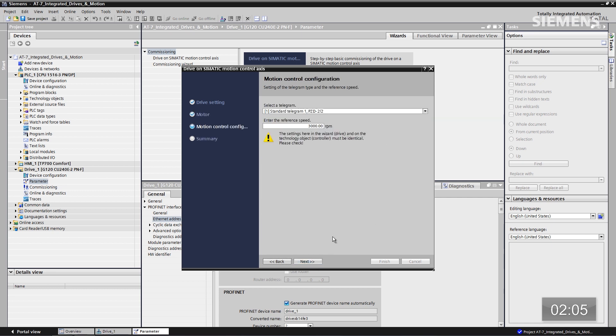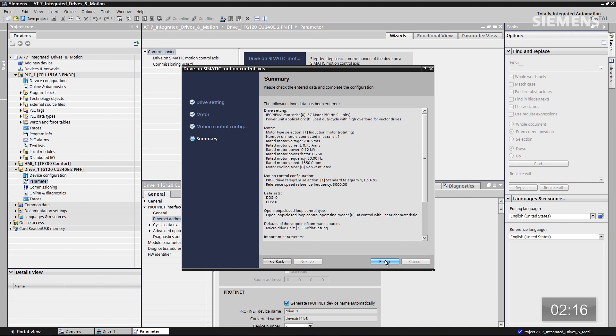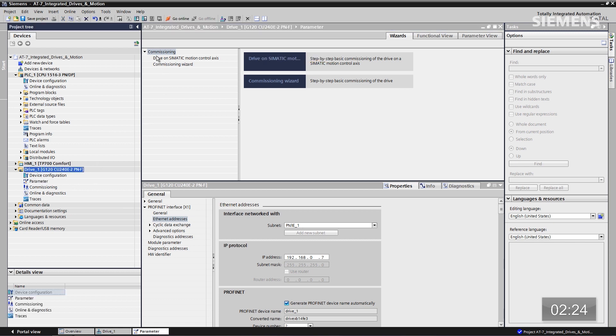Let's click on next. Here we could change the telegram that we're sending and receiving, as well as the maximum RPM, which is 3000 — we'll leave the defaults. Let's click on next again. And there's the summary. I like everything I've done, so choose Finish. Parameterization is done. So now I can actually give focus to the G120 drive.